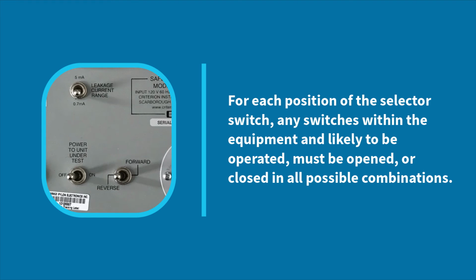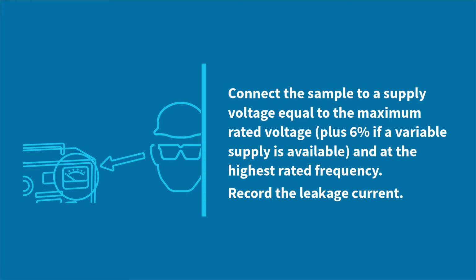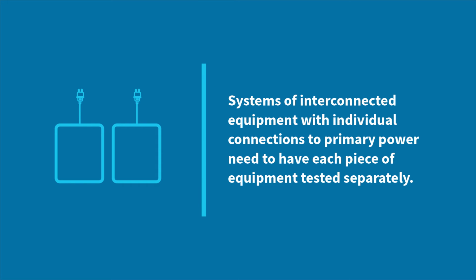For each position of the selector switch, any switches within the equipment and likely to be operated must be opened or closed in all possible combinations. Connect the sample to a supply voltage equal to the maximum rated voltage plus 6% if a variable supply is available, and at the highest rated frequency. Record the leakage current.